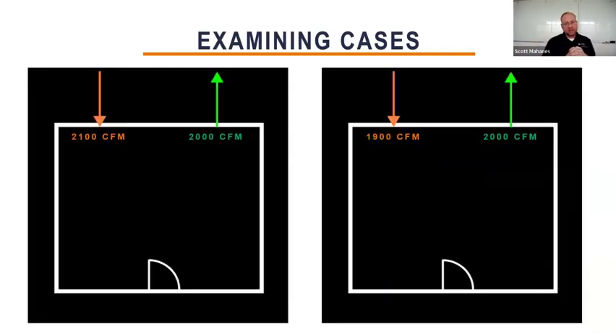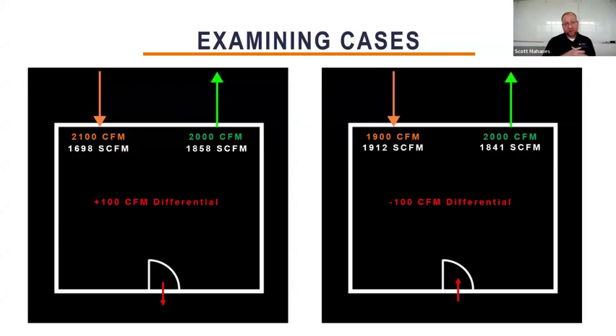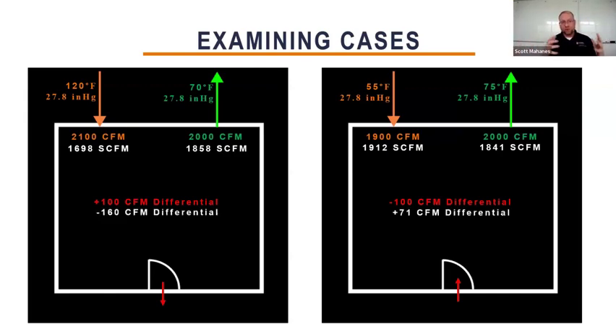Another thing where this kind of becomes an issue is room pressurization. We believe that room pressurization is a volumetric flow rate difference controlled by volume difference. And on the left, you'll see that I have a positive 100 CFM differential, and on the right, a negative 100 CFM differential. And you would think that respective to a neutral space, you would have a positive pressured room on the left and a negative pressure room on the right. However, if you look at it from a mass flow perspective, which really drives the room pressure under these conditions, which would be like 3,000 feet above sea level at these temperatures, you'll see that I have a very different CFM value, and the differential of those values actually goes really, really far off.